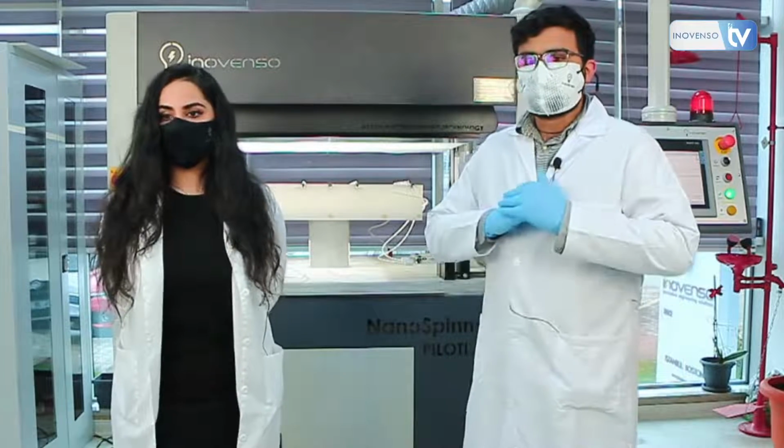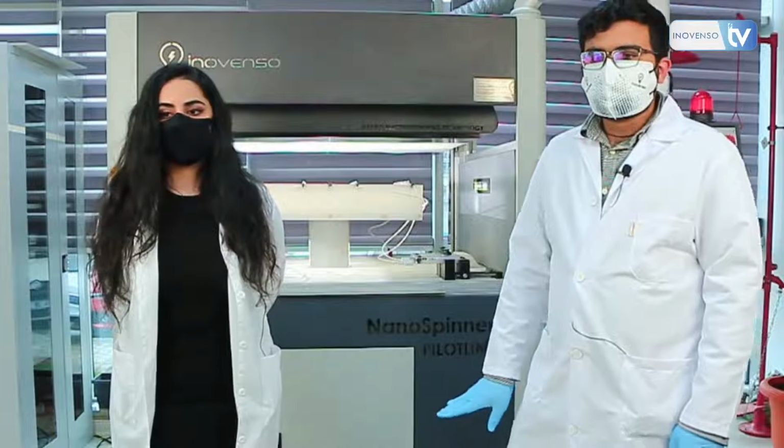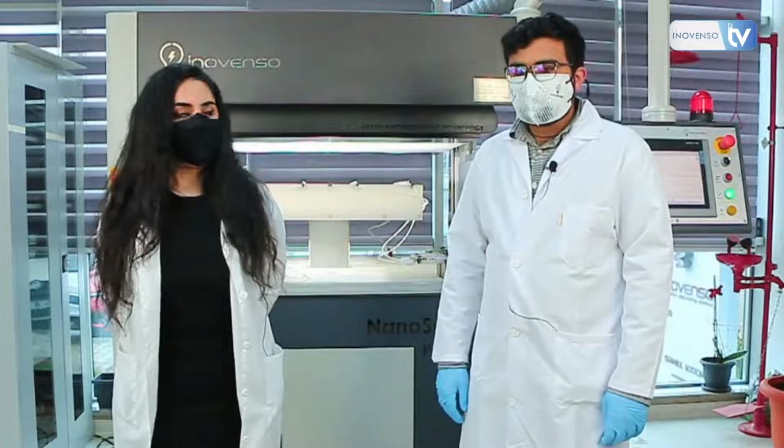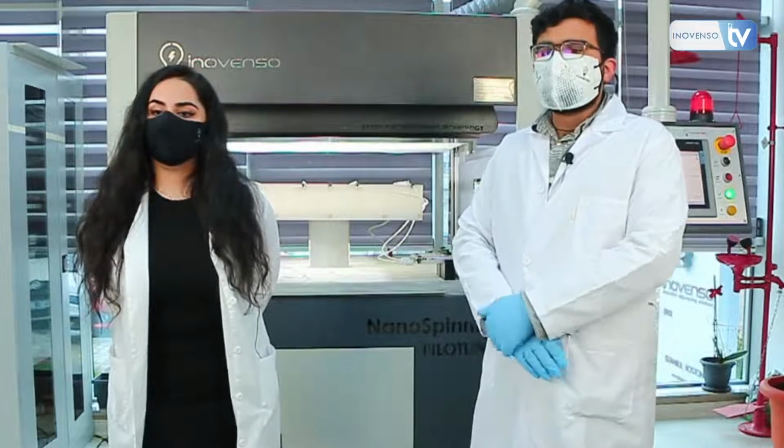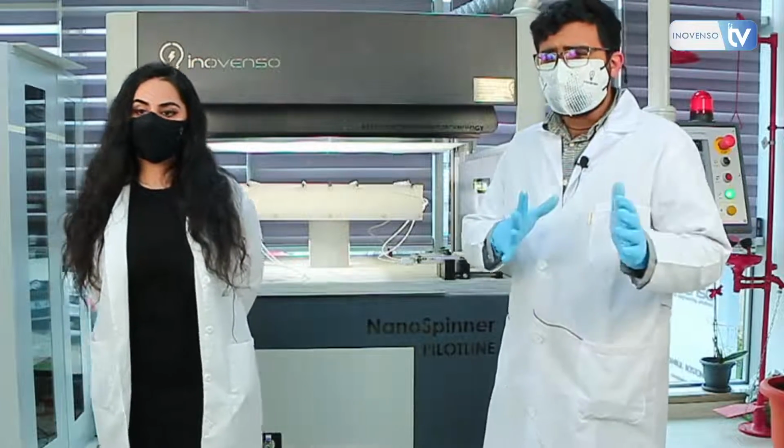Yes, so we have another question right here. What is the optimum fiber size for an air filtration membrane? Okay, so for the air filtration membrane, in our experience, it's about 50 to 300 nanometers.